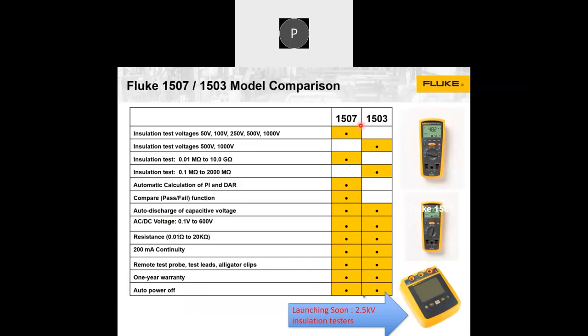These two models are actually very popular insulation testers from us. You can see the insulation test voltages, and with a single press you will be able to get the voltage level you want. The 1507 and 1503 will give you specific voltage levels. Even the 03 model can give you two voltage levels, 500 and 1000 volt. Here you can get multiple choices, from 50 volt to 1000 volt ranges.